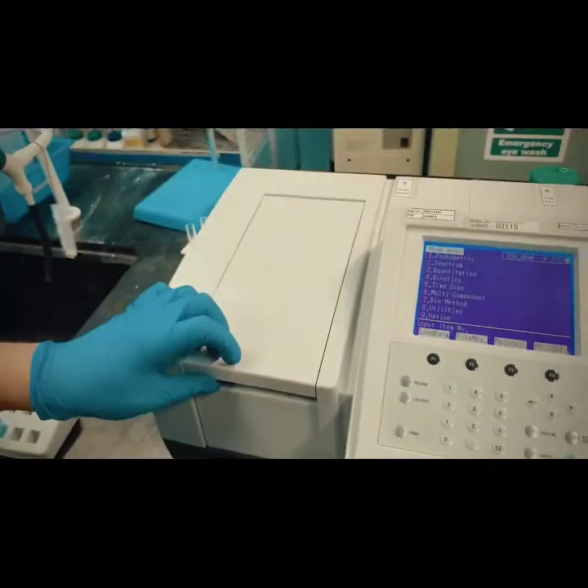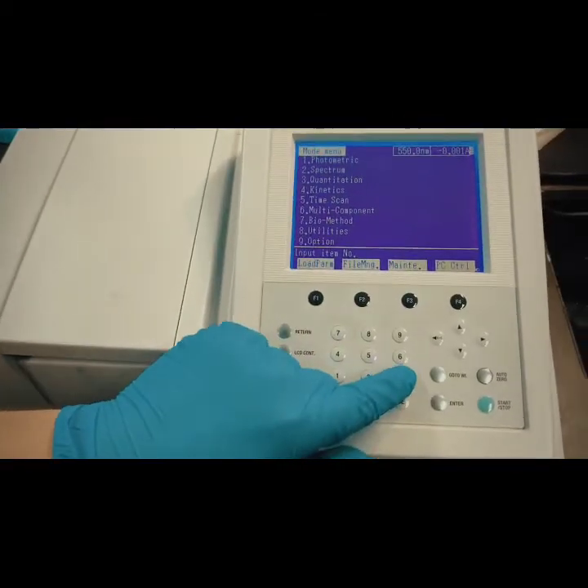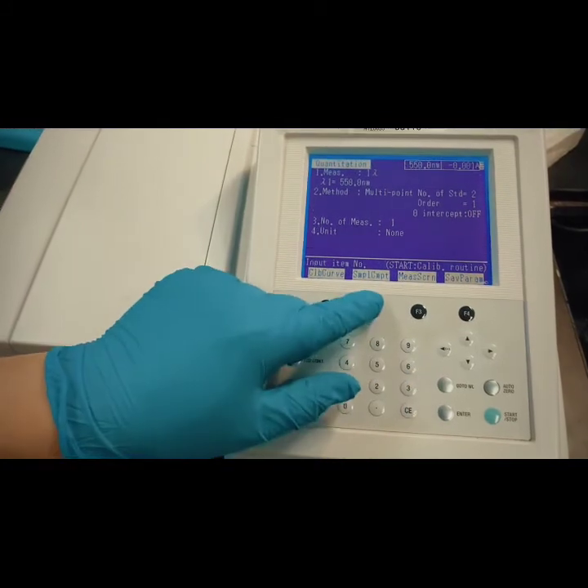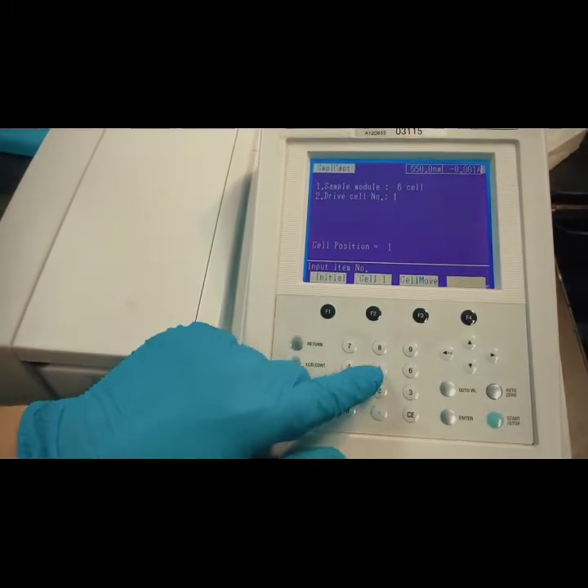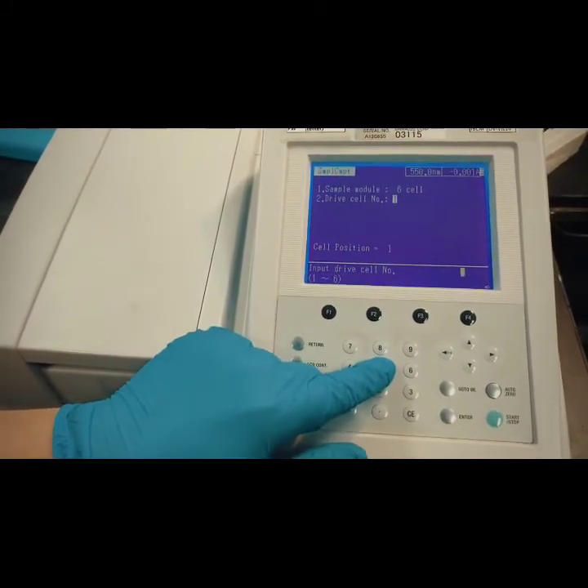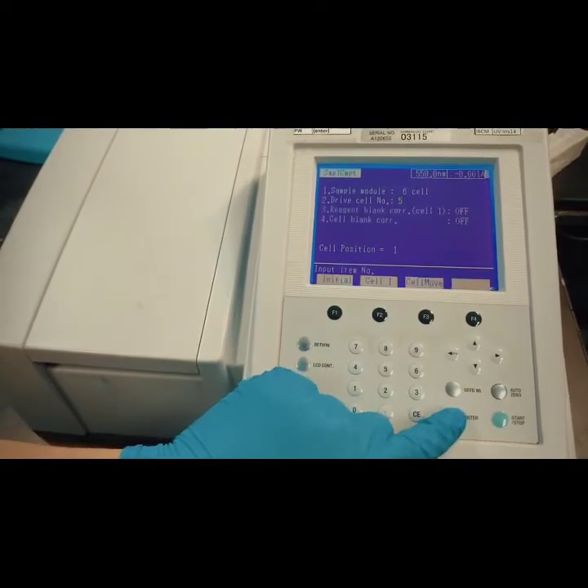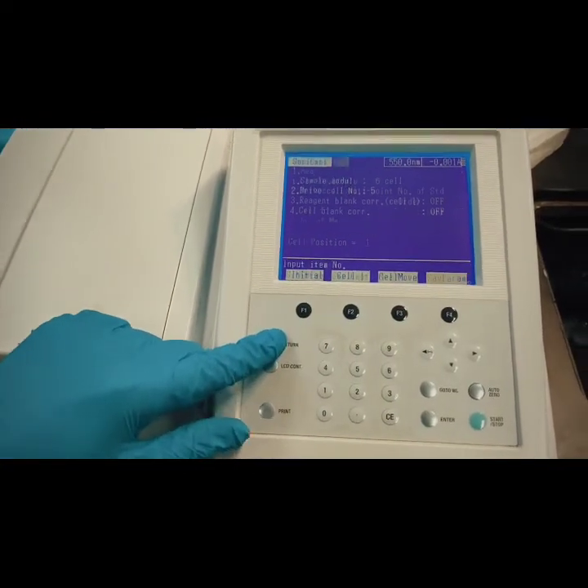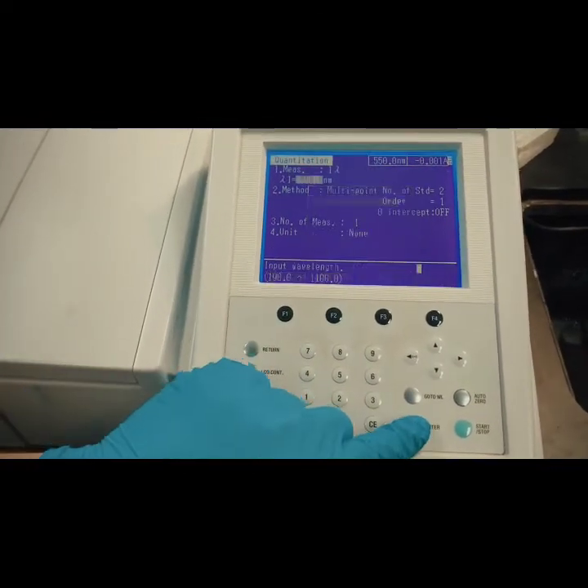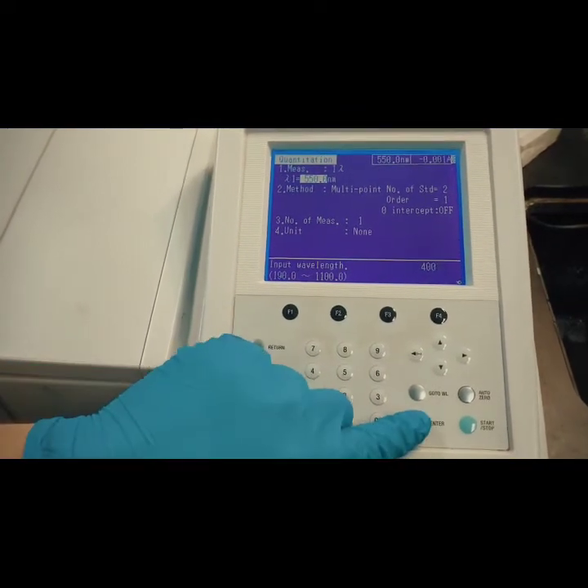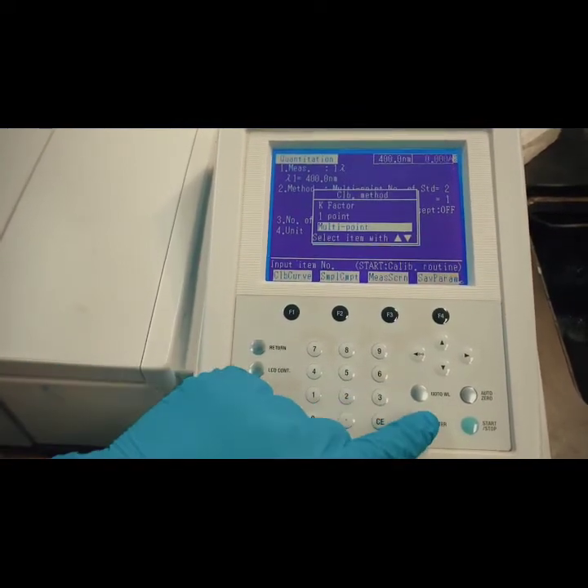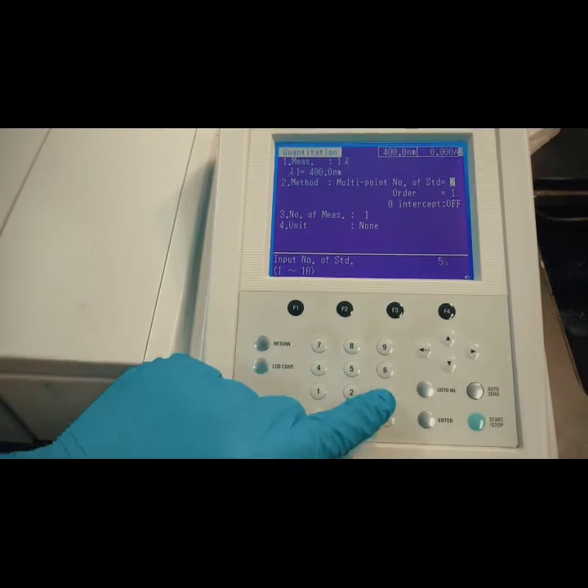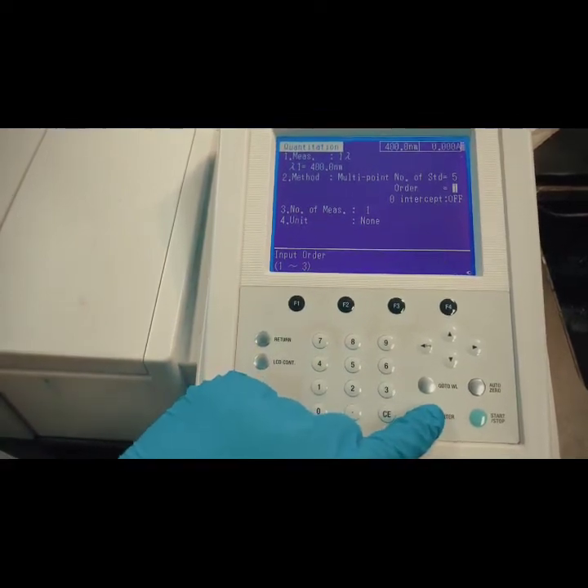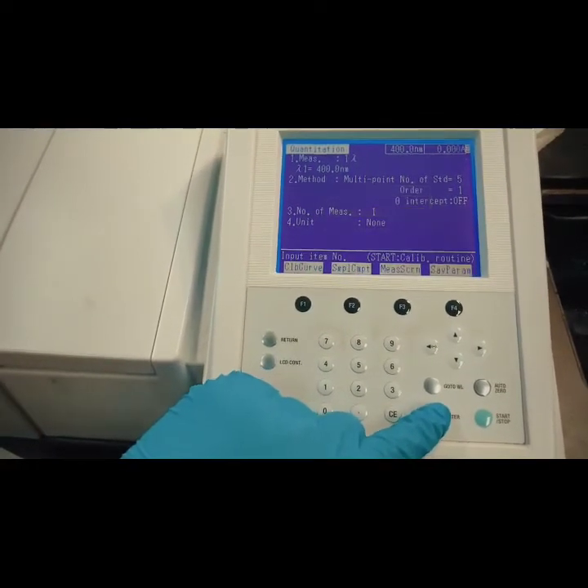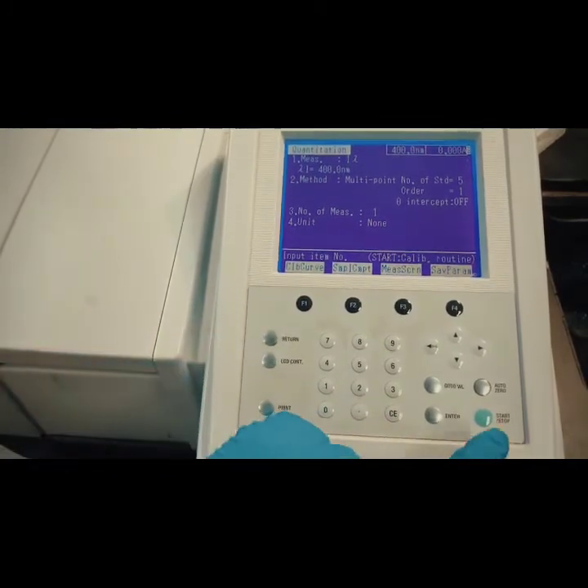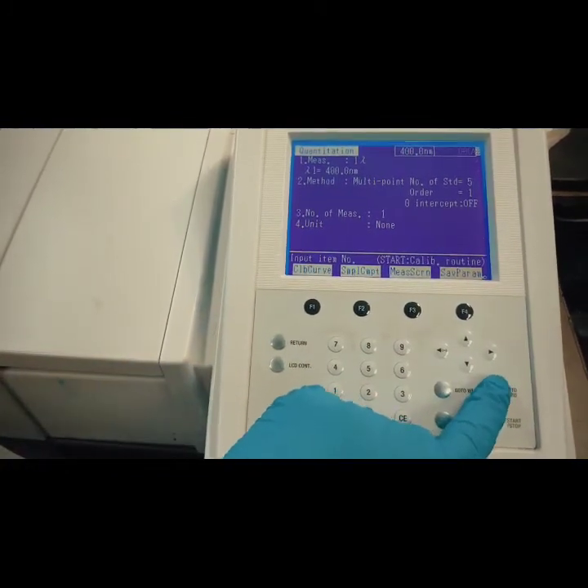Insert a blank cuvette into the machine. Select Quantitation, Sample Compartment, and adjust the drive cell number to the number of cuvettes you are going to use. Return to the previous page, select Measure, enter 1 lambda, and adjust the required input wavelength. Now select Method, Multi-point, and adjust the number of standard solutions. Press Enter and select Zero Intercept as off. Select Auto Zero to begin the calibration process.